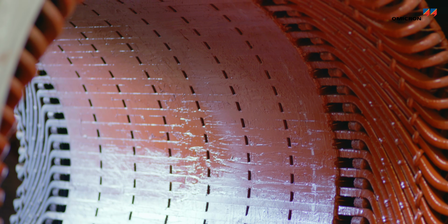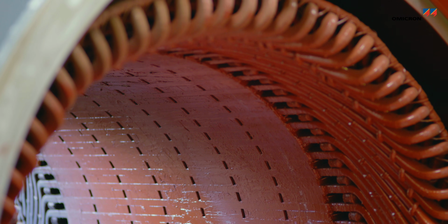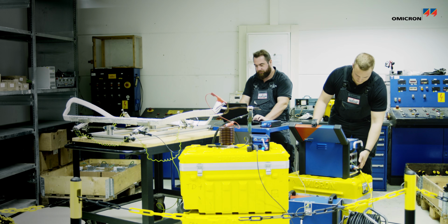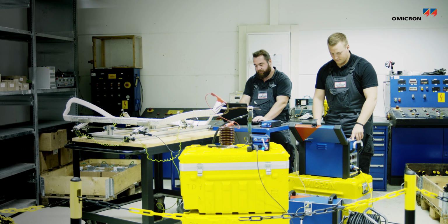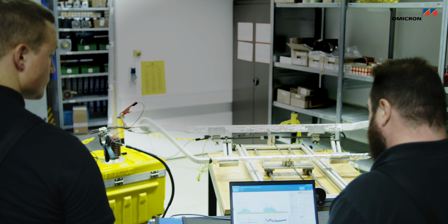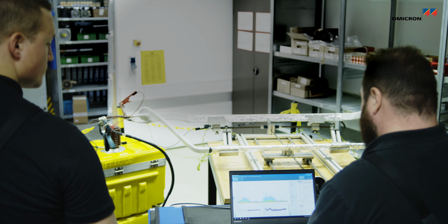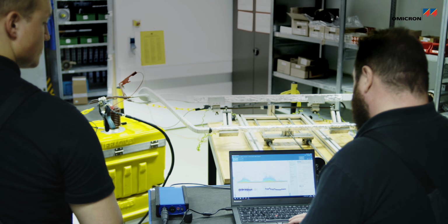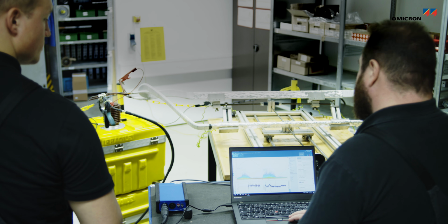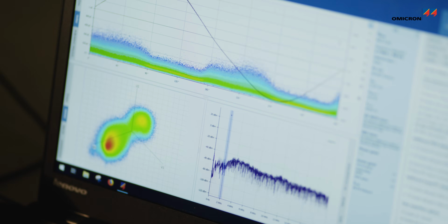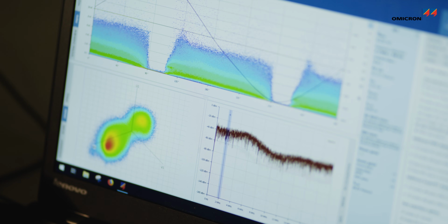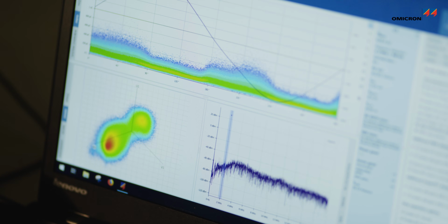The insulation materials typically used for rotating machines are resistant to a certain level of PD over a length of time. However, an increase in PD activity at certain voltage levels can either indicate defects incurred during the manufacturing process or insulation deterioration when in service. PD measurements allow single weak points of the insulation system to be clearly identified.